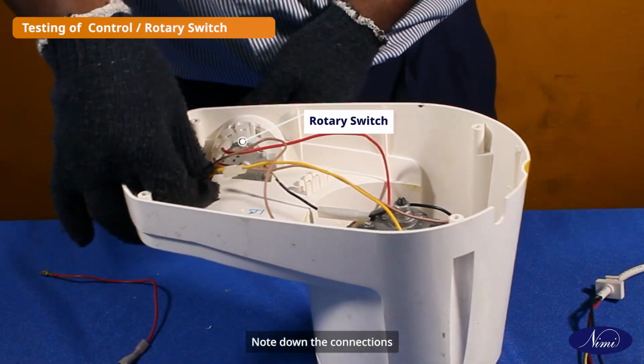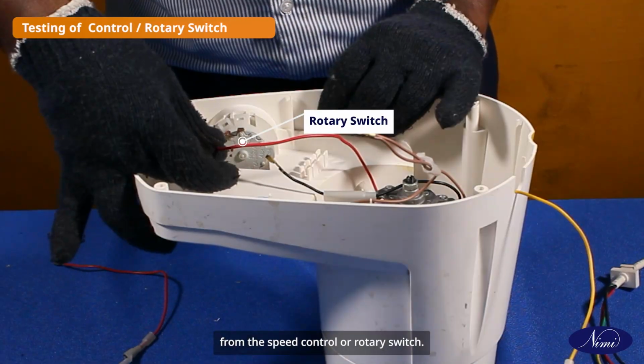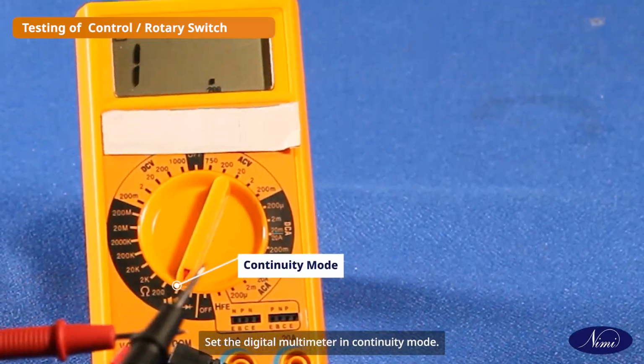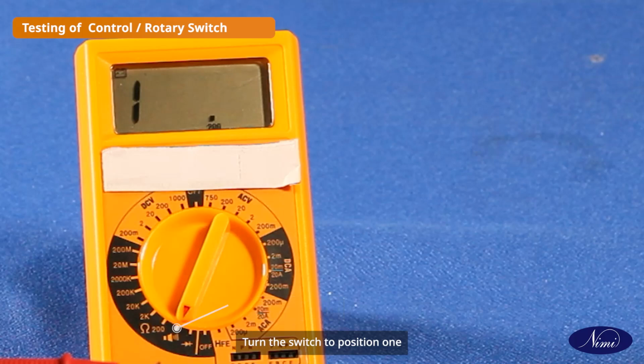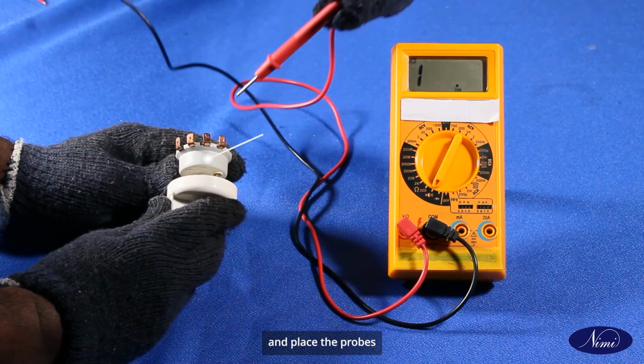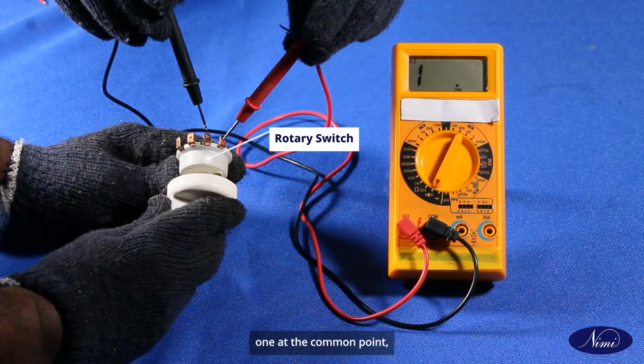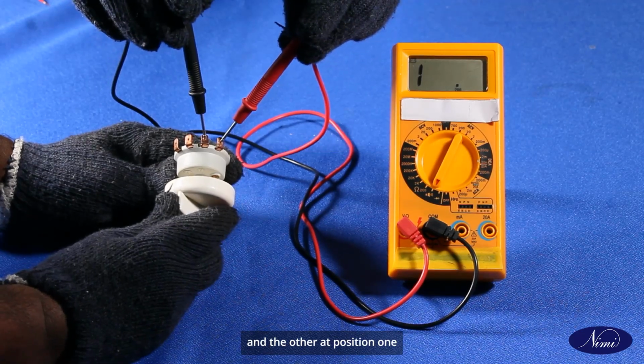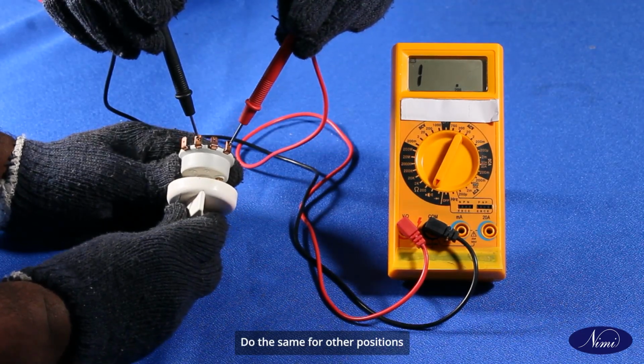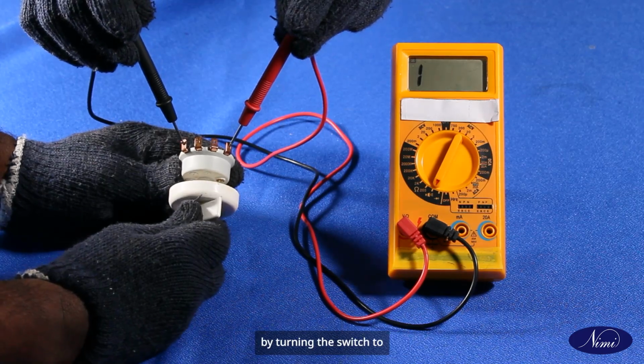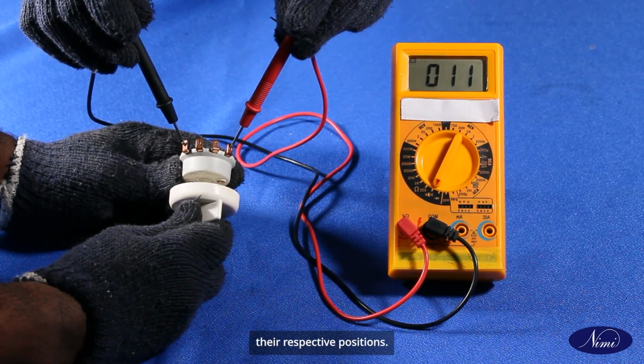Note down the connections before removing the connection from the speed control or rotary switch. Set the digital multimeter in continuity mode, turn the switch to position 1 and place the probes, one at the common point and the other at position 1, and check the continuity. Do the same for other positions by turning the switch to their respective positions.